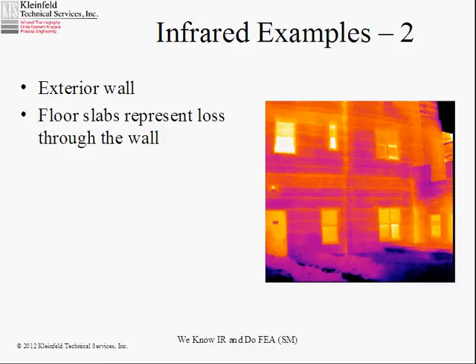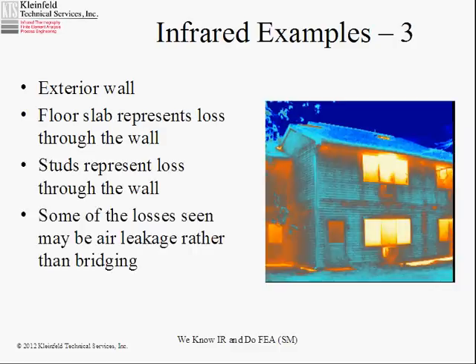This is an exterior wall. There's a concrete slab floor here, and concrete is fairly conductive. When it's connected directly to your outside wall, it's going to represent a heat loss. If you look at infrareds in cold weather on the outside of buildings with almost any kind of wall construction, you will see this — and that represents a thermal bridge and a heat loss.